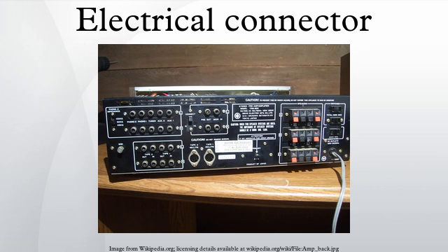Types of electrical connectors. A terminal is a simple type of electrical connector that connects two or more wires to a single connection point. Wire nuts are another type of single-point connector. Terminal blocks. Terminal blocks provide a convenient means of connecting individual electrical wires without a splice or physically joining the ends. They are usually used to connect wiring among various items of equipment within an enclosure or to make connections among individually enclosed items. Since terminal blocks are readily available for a wide range of wire sizes and terminal quantity, they are one of the most flexible types of electrical connector available.